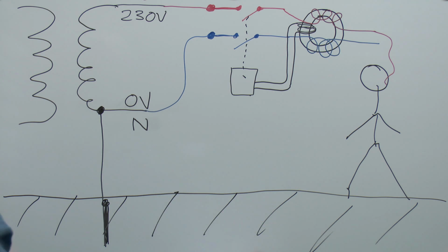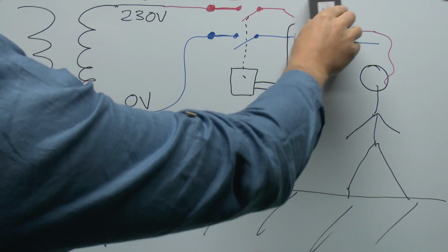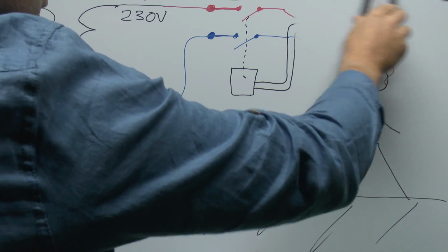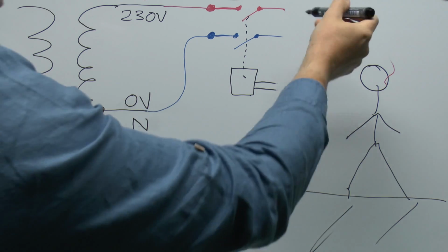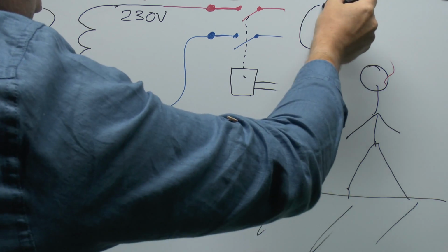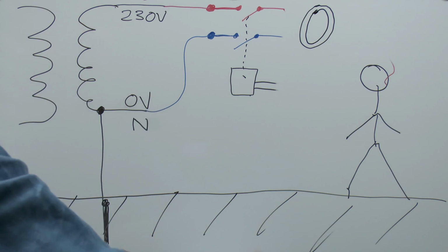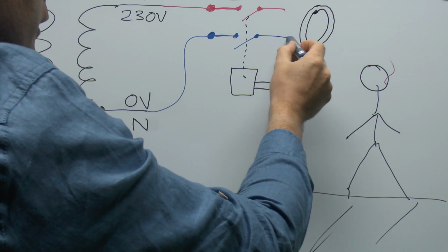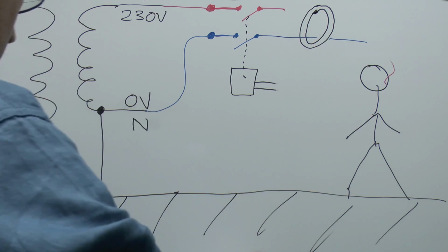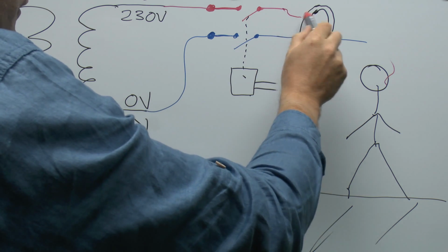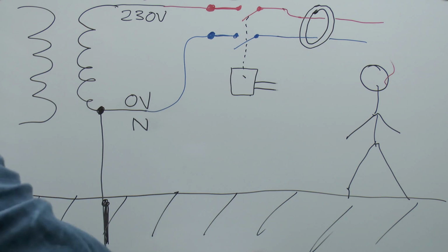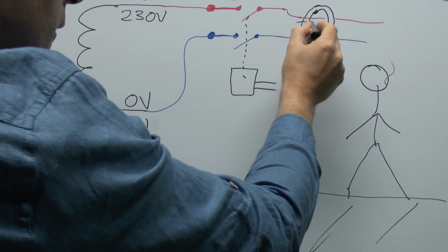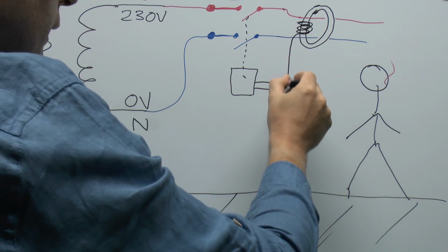expensive. So most modern RCDs are not actually made in that fashion, so we'll just erase that away, and we'll just draw that in again with the more likely scenario. The usual way now is to still have a magnetic core made out of ferrite or some other material, but instead of actually winding them around, the two wires actually just go through the centre, and of course the line will go through the centre just the same, and again that goes off to your load or whatever. The sensing coil is basically still the same, and that would just go around the core like that.